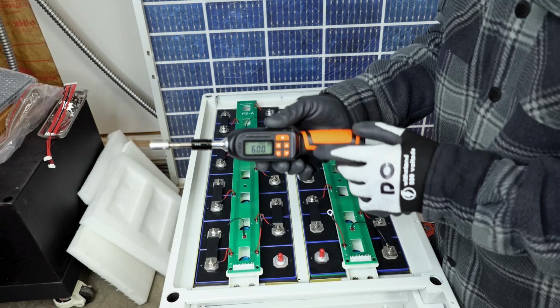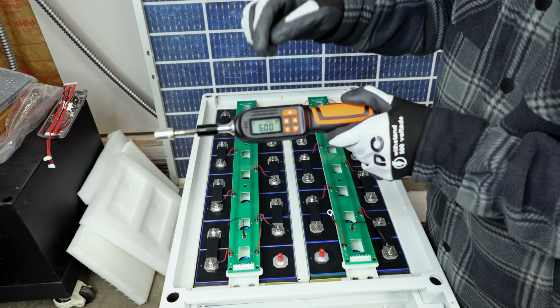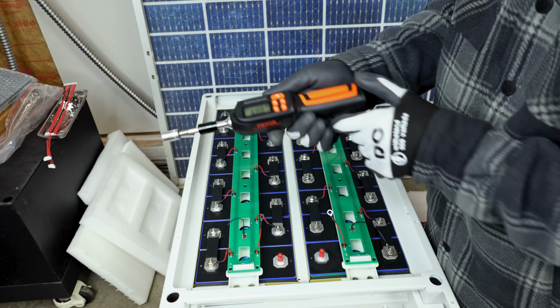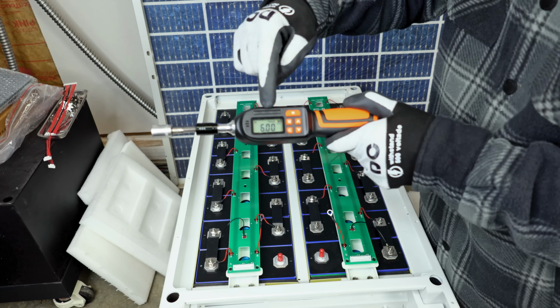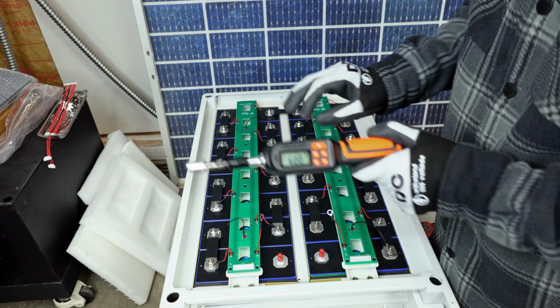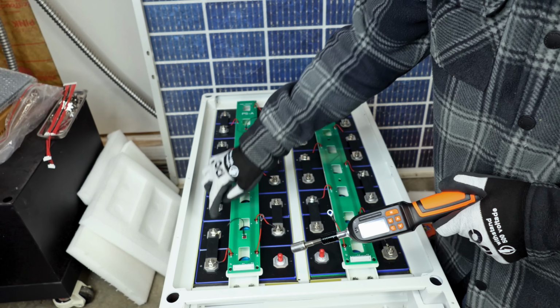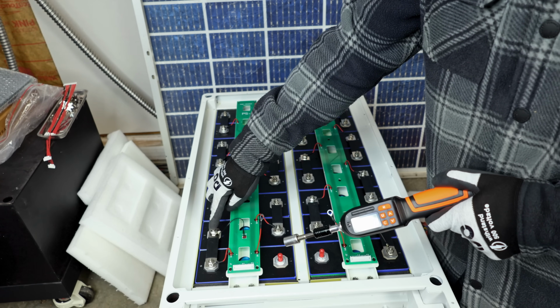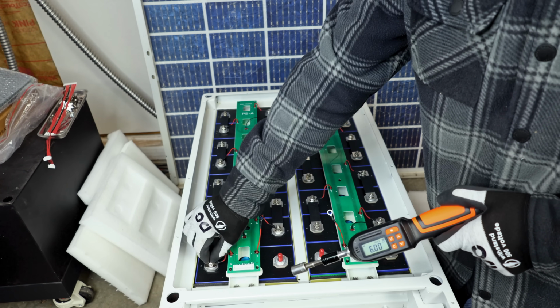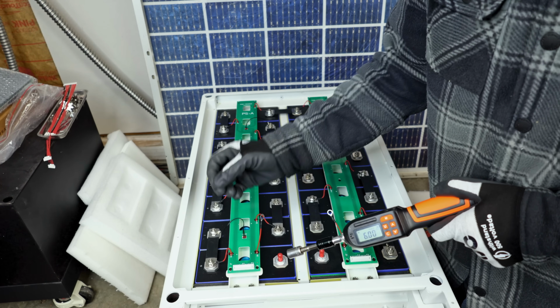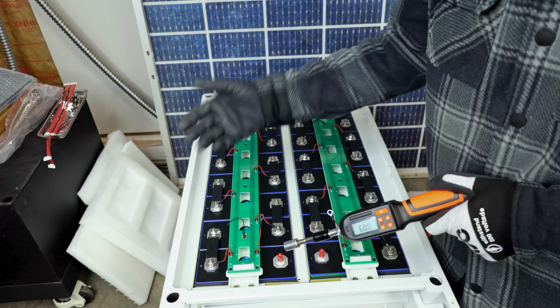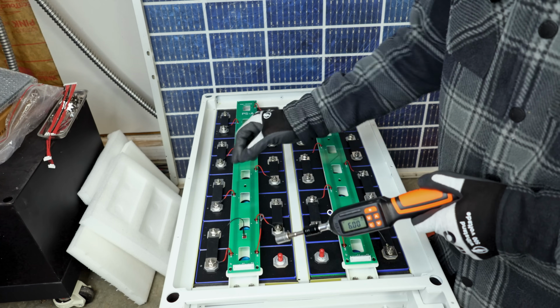When you make these connections, you're going to want to use a torque wrench. In this case I'm just using a torque screwdriver, set to 6 Newton meters. If you don't set the torque properly, you'll have either too much or too little. Too much torque and you could break the studs. Too little and you'll have a high resistance joint that could lead to heat and damage to the battery or incorrect measurement.